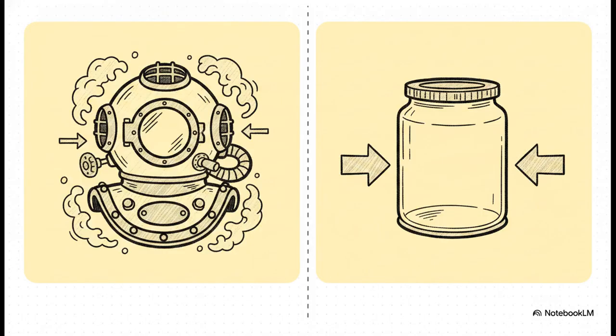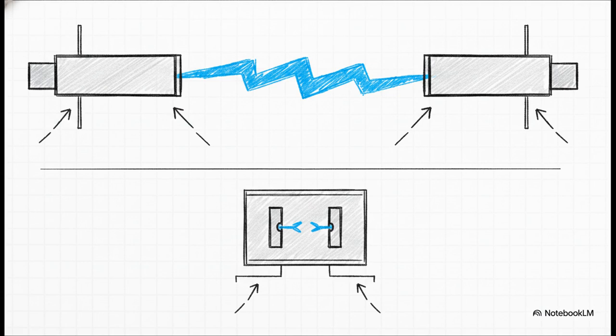Now, the underlying physics here are actually pretty fascinating when you compare GIS to the other major technology we use, vacuum circuit breakers, or VCB. Think of it like this. GIS is basically a pressurized diving suit. It survives those extreme hostile voltages by pumping in a specialized protective medium, specifically sulfur hexafluoride, or SF6 gas. On the totally opposite end of the spectrum, VCB operates like a vacuum-sealed container. Instead of adding a protective medium, it just removes the medium entirely. It uses a near-total vacuum to instantly kill the electrical arc. So you've got two totally different principles achieving the exact same goal: safely breaking an electrical circuit in a tiny footprint.